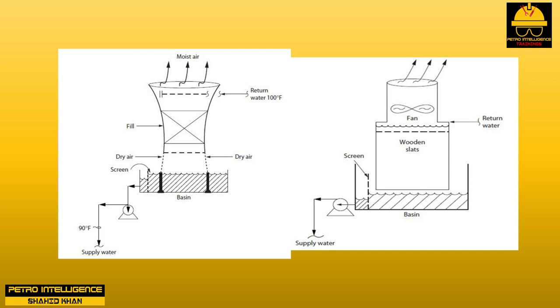Cooling tower efficiency: two types of cooling towers are in widespread use — natural draft and induced draft. The giant natural draft towers are used in Europe and in nuclear power plants; I've only worked with these towers in one refinery and their performance was poor. Air flow is generated by the air inside the tower being heated by the warm cooling water; also, the molecular weight of evaporated water is less than the molecular weight of air, so a few tenths of an inch of water draft may be developed. The much smaller induced draft cooling towers are used in process plants, with air flow generated by large induced draft fans.